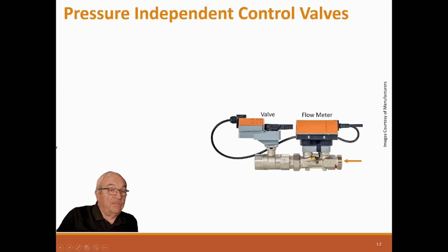So here's these valve assemblies. This is a Belimo, of course, and it's got a control valve here, and it's got a flow meter upstream. What happens is the control system tells the flow meter how many GPM I need, and then it modulates this valve to maintain that flow. They're really slick. They're really expensive, but they're really slick. Because these are totally pressure independent, think of this as a pressure independent VAV box for water, basically. So it's fairly good. I like them.